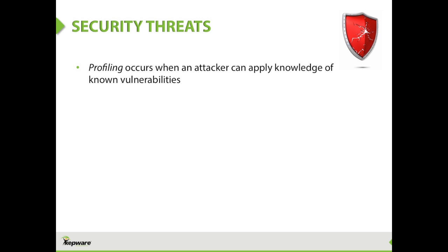And then ICS CERT will go out and say, okay, we discovered this vulnerability in this piece of hardware, software, this model number, this firmware revision, everything the customer would need to know to identify the equipment at their site that has the issue. And the intention is that by broadcasting that, everyone who manages these sites will say, okay, we've got to go patch these systems to remove this vulnerability. And that's great. We need that, right? But inevitably, it's a little more difficult than that. These sites have 24-hour uptime requirements. Sometimes there's a mentality that we're small and we're not going to be attacked, so why would we bother applying all these patches? So at the end of the day, the patches sometimes don't get applied.